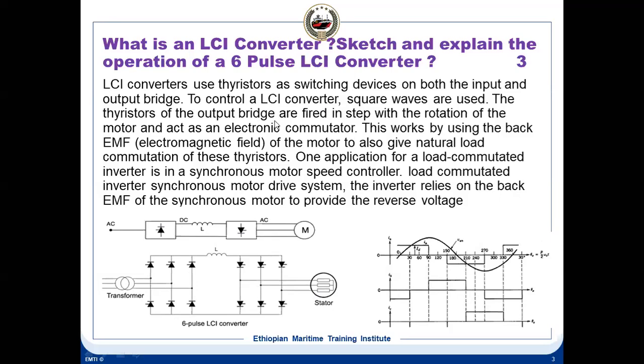The thyristors of the output bridge are fired in step with the rotation of the motor and act as an electronic commutator. So this works by using the back EMF of the motor to also give natural load commutation. Okay. So an application of a load commutated inverter is a synchronous motor speed controller, the load commutated inverter synchronous motor drive system. The inverter relies on the back EMF of the synchronous motor to provide reverse voltage.